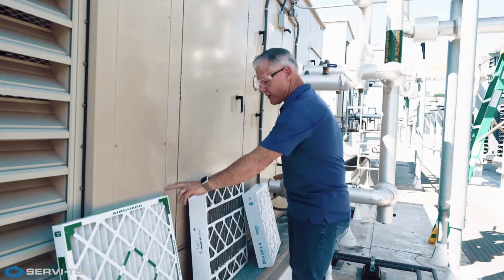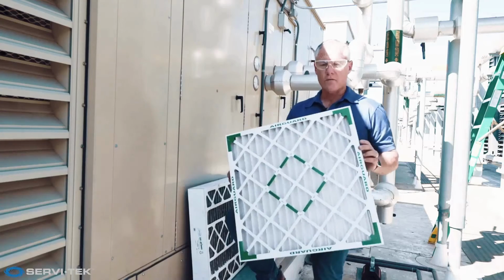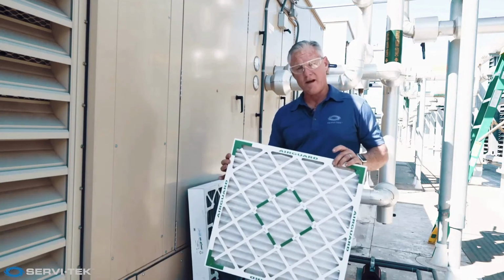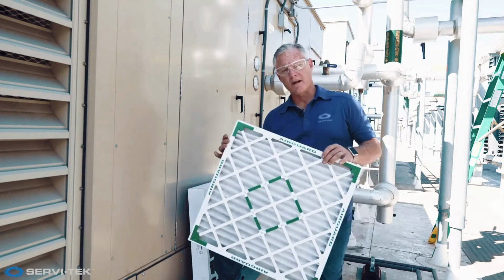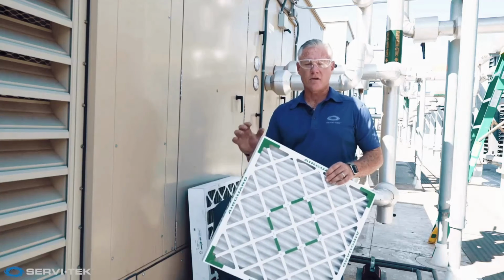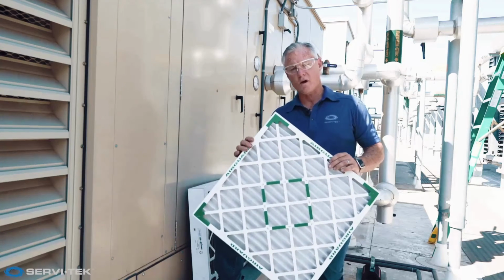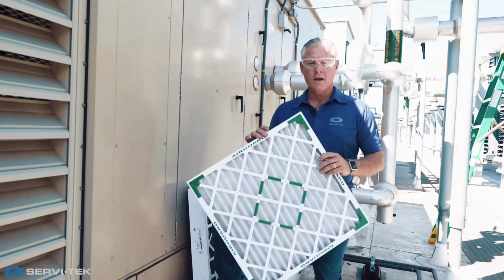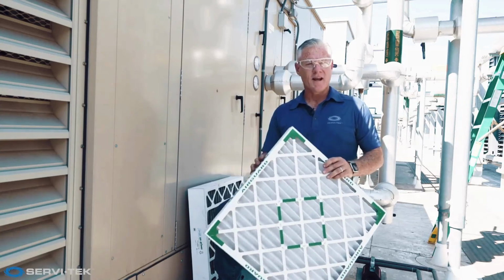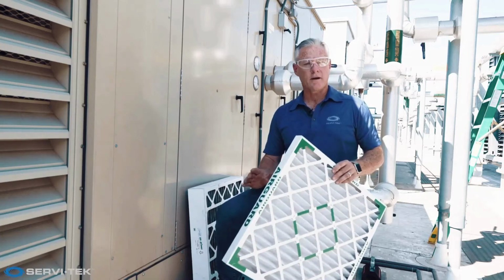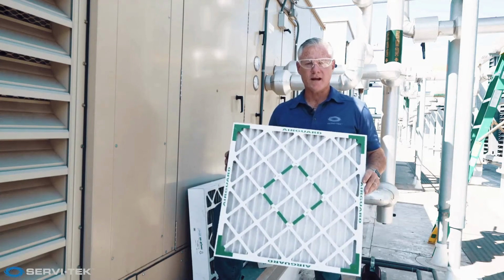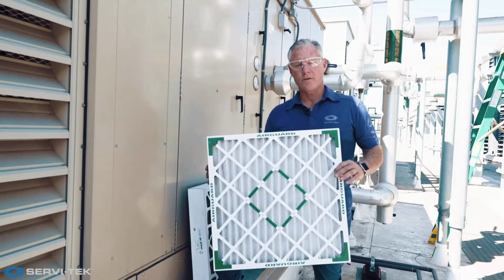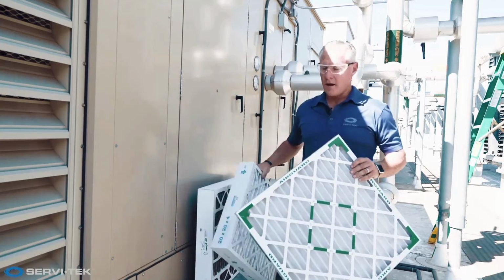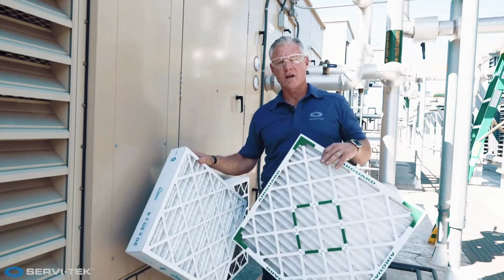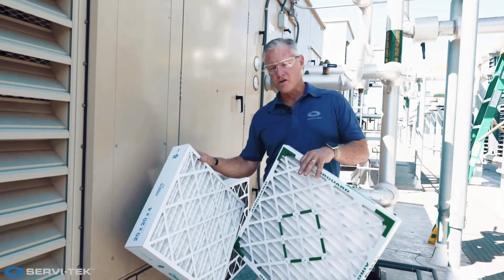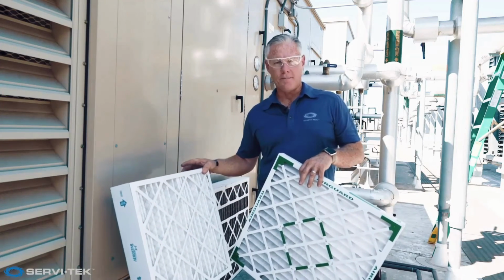This particular filter here is a MERV 8 rated filter. There is nothing wrong with this filter. The fact that it's not MERV 13 rated, though, means that a lot of buildings are moving away from this, simply because tenants are looking for something that's got a little bit better filtration quality, a little more indoor air quality focused on the filtration. That doesn't mean that anything we were doing previously was wrong. Everything was great. Filters are meant to protect equipment as much as they are to protect people. When you start putting in higher efficiency filters, you're also causing more resistance on your fan, more energy consumption, but you know what? You're going to have a happier tenant.